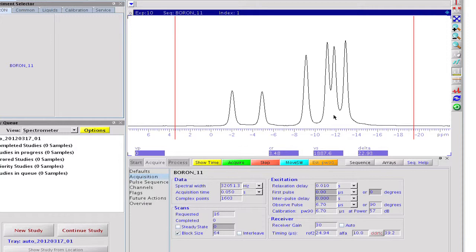While customizing the parameters, we requested a 90 degree excitation pulse. But our probe file does not contain calibration data for B11 yet. The pulse width that we just used was a leftover from the C13 parameter set. Now that we have a working B11 protocol, we can quickly perform a pulse calibration.